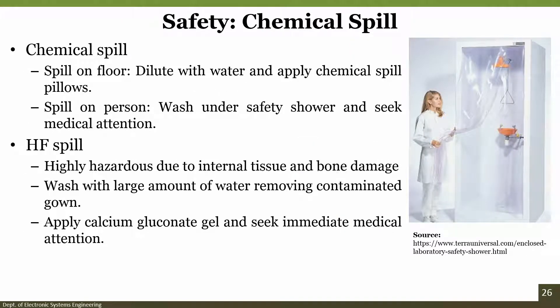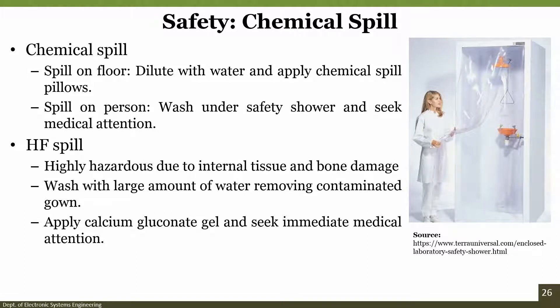If there is a chemical spill on the floor, dilute with water and use chemical spill pillows available in the clean room. If there is a spill on a person, wash under a safety shower and seek medical attention. The most dangerous spill is an HF — hydrofluoric acid — spill, which is highly dangerous due to internal tissue and bone damage. Wash with large amounts of water, remove the contaminated gown, apply calcium gluconate gel, and seek immediate medical attention.